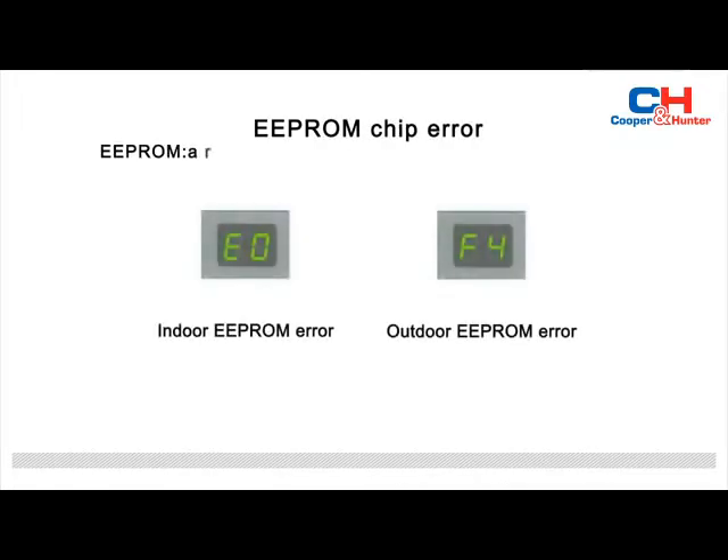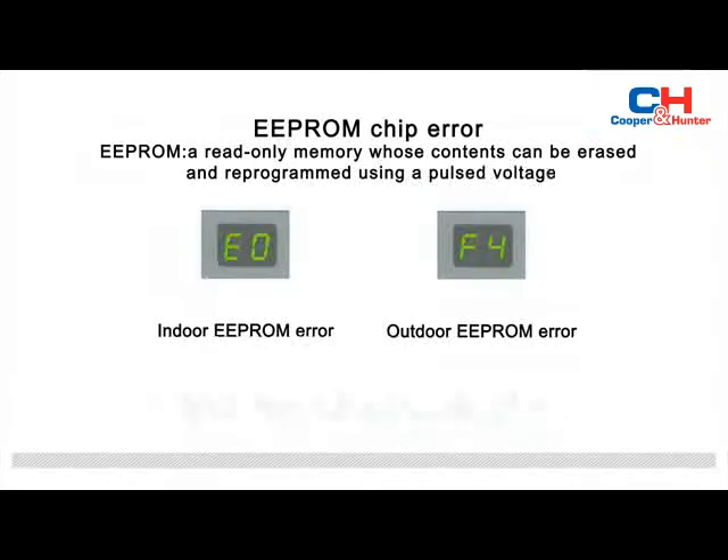When the display board of the indoor unit displays E0 or F4, that indicates EEPROM chip error. EEPROM is a read-only memory whose contents can be erased and reprogrammed using a pulsed voltage.